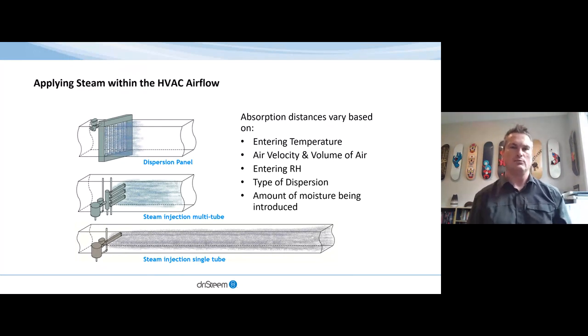Something to note when we apply steam within the HVAC airflow is absorption distance. That's the distance it takes for the steam to absorb completely in the air so that it doesn't wet the surfaces of the air handler or the ducted network. Things we need to consider in applying this type of technology are the entering air temperature, the air velocity, and the volume of air that you're trying to introduce, and the entering air RH, because if the air is currently very saturated, it's going to be more difficult for that air to continue to hold moisture and, in effect, make the absorption distance longer. The type of dispersion being used will also drastically change the length or time it takes to absorb that moisture. If we're using a single tube, for example, it may take longer for that steam to absorb than if we used multiple tubes within a dispersion panel. And then the amount of moisture being introduced.